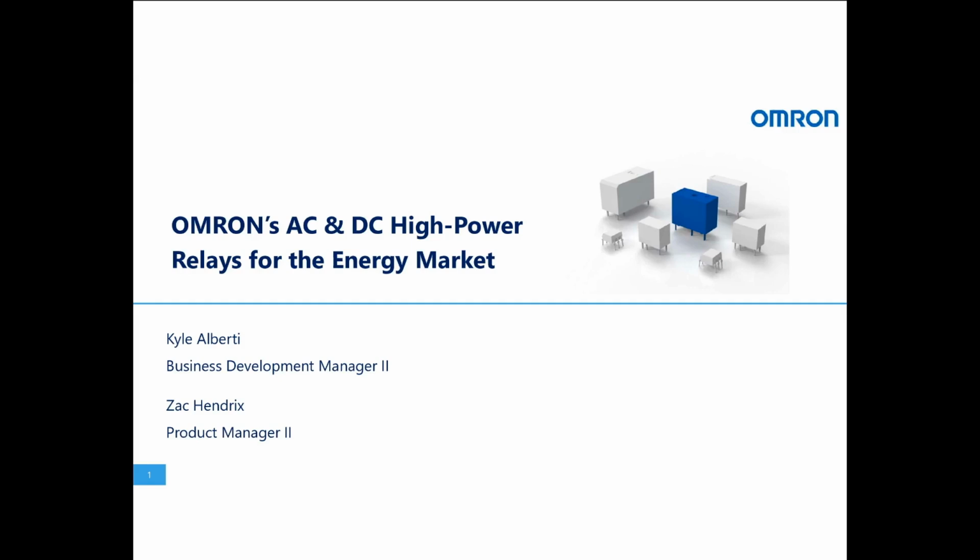So just to give you a little flavoring, we have electromechanical and solid state relays for switching below 3 amps. So this is like test and measurement type relays, both multi-pole and single pole relays, latching and non-latching. And then the most prevalent section is our power PCB relays. So that's the mid-current range from 3 to 40 amp switching. And that's form A, B, and C contacts. So transfer contacts are just open closed.